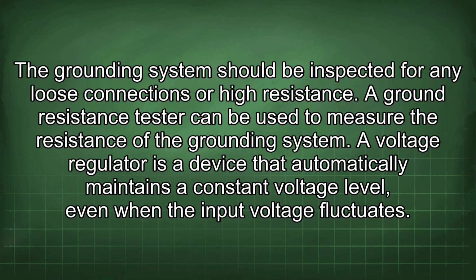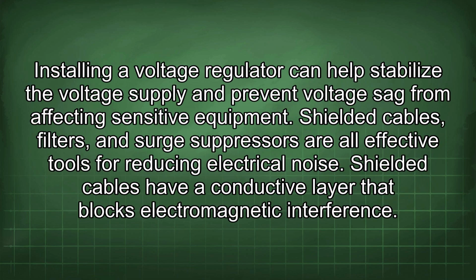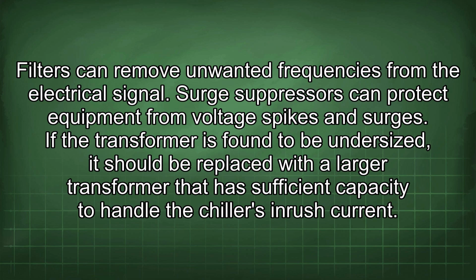A voltage regulator is a device that automatically maintains a constant voltage level, even when the input voltage fluctuates. Installing a voltage regulator can help stabilize the voltage supply and prevent voltage sag from affecting sensitive equipment. Shielded cables, filters, and surge suppressors are all effective tools for reducing electrical noise. Shielded cables have a conductive layer that blocks electromagnetic interference. Filters can remove unwanted frequencies from the electrical signal. Surge suppressors can protect equipment from voltage spikes and surges.